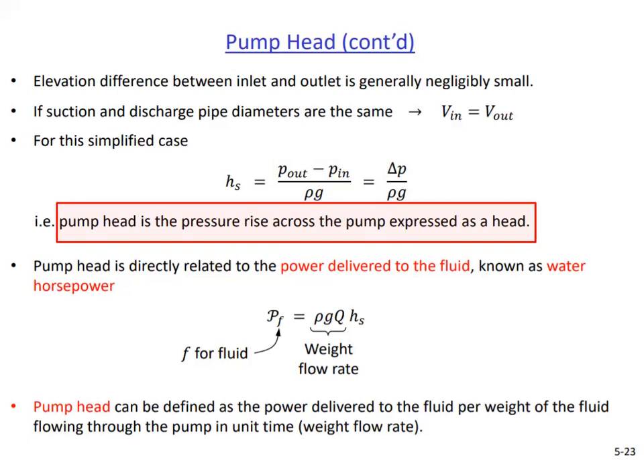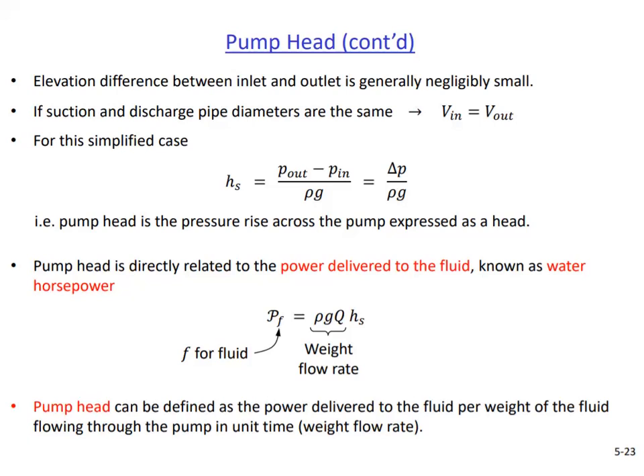Pump head is nothing but the pressure rise across the pump expressed as a head with the units of length. Here it's worth remembering that this equation is valid when the elevation and velocity head differences are negligible, which is not necessarily the case, although seen very commonly.